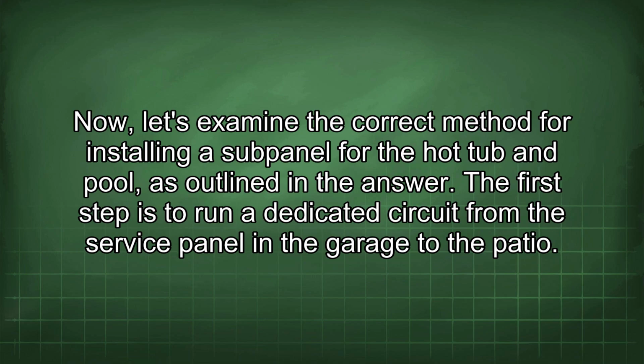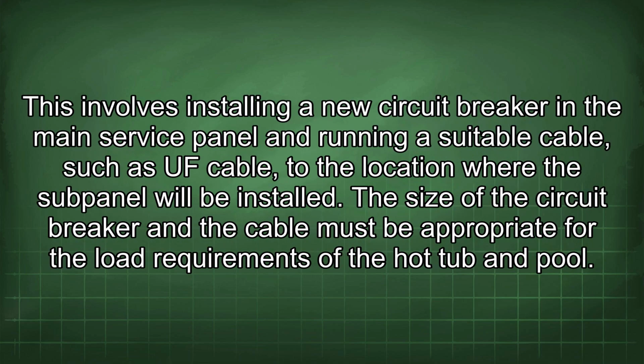Now let's examine the correct method for installing a subpanel for the hot tub and pool, as outlined in the answer. The first step is to run a dedicated circuit from the service panel in the garage to the patio. This involves installing a new circuit breaker in the main service panel and running a suitable cable, such as UF cable, to the location where the subpanel will be installed.